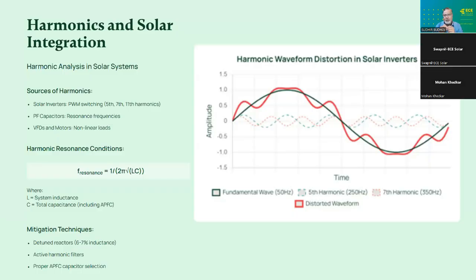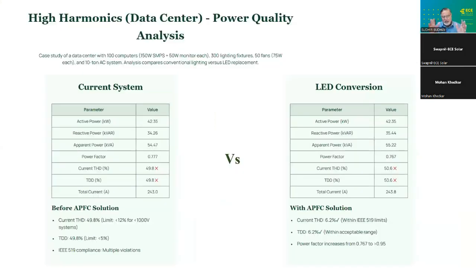So let's take a quick example of a harmonic situation. Let me make it a little loud, like what we saw in the unbalanced case, like the 12 to 45 ampere kind of variation. Similarly, let me take an extreme case in harmonics, just for the sake of demonstration. Let me take a data center which is prone to this kind of harmonics, plus we are adding solar. Suppose there are 100 computers, 100 monitors, 300 lighting fixtures, 50 fans, and a few ACs running. Plus, they had APFC, because the air conditioning load is there.